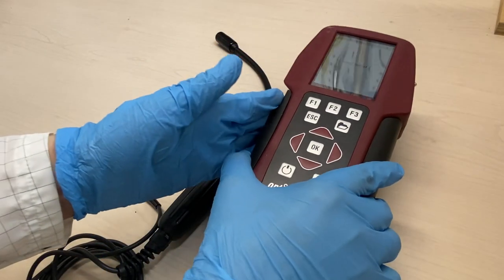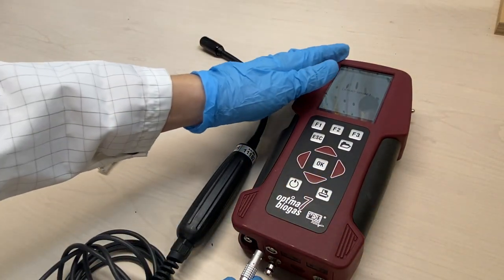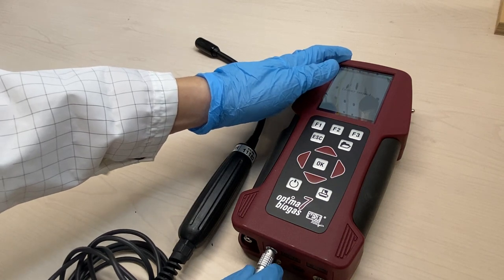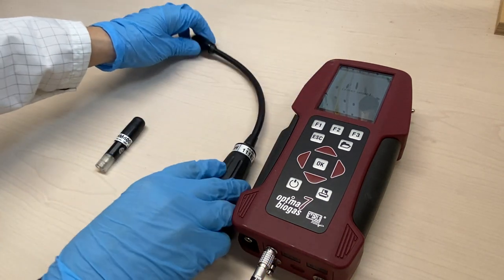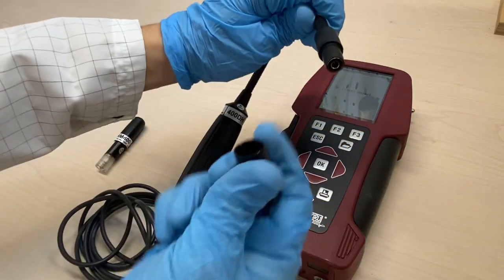Attach the sensor probe to the auxiliary port, making sure the red dot on the probe aligns with the red dot on the auxiliary port. Do not forget to remove the protective cap from the sensor.